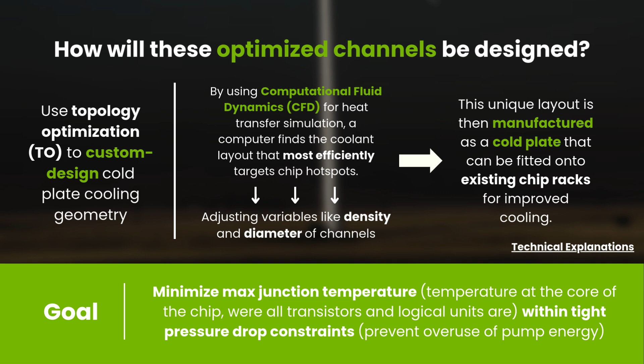This isn't theoretical. A published study from August 2024 proves this approach. Their hotspot-aware cold plates reduced chip temperatures by 13% and pressure drop by 55% compared to conventional designs. Large data centers save 3 to 6 megawatts of cooling power, equivalent to $2 to $5 million in annual energy costs per site. They also improved hardware longevity by reducing heat-induced stress.